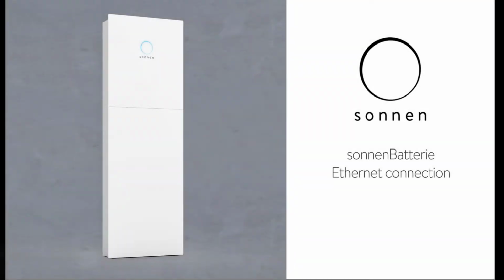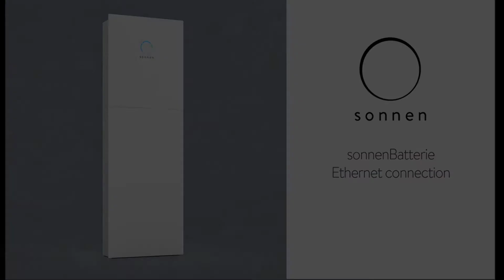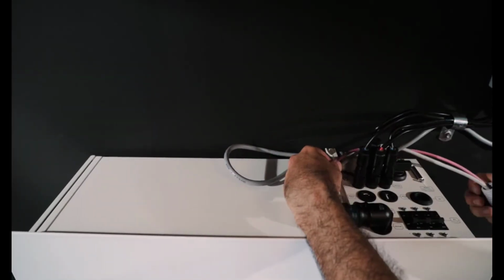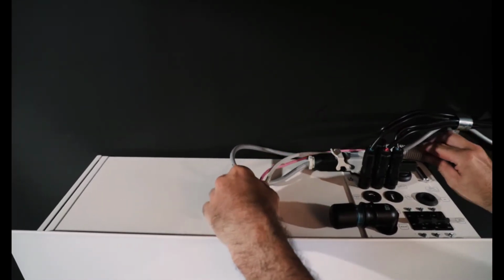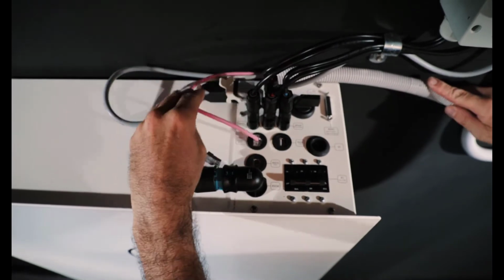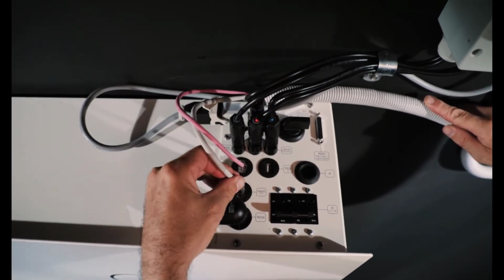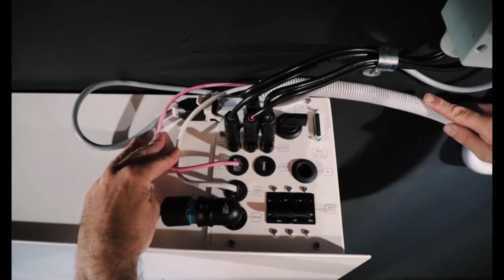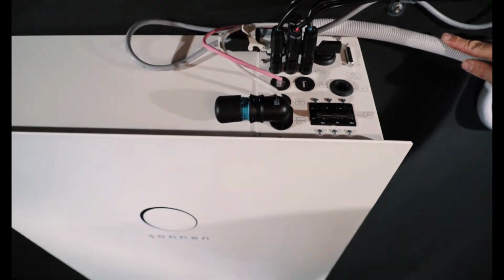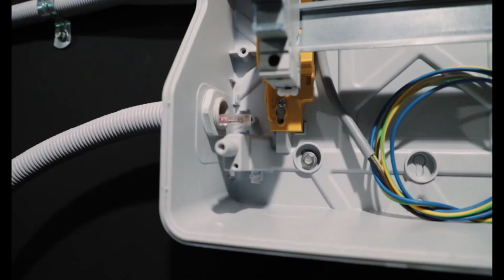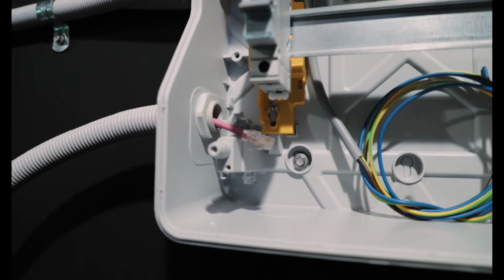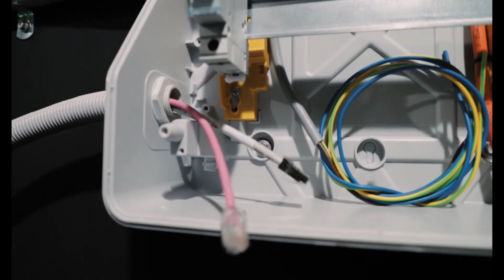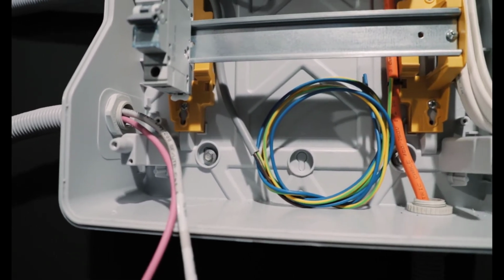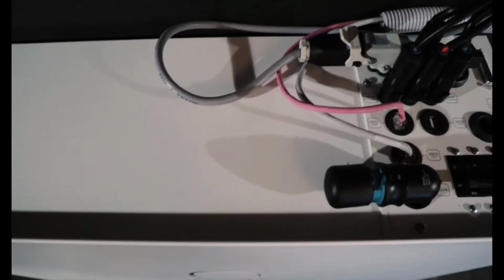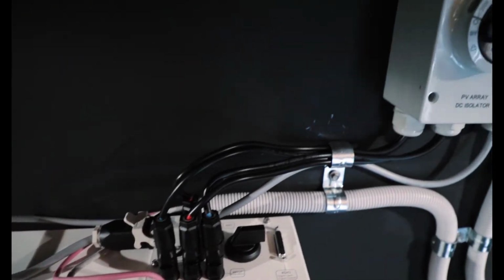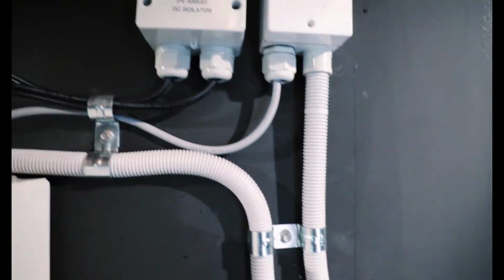So before we go on to any of the metering and CTs, let's have a quick look at the Ethernet connection. What I'm illustrating here is both the Ethernet and the Modbus connections. Ethernet being the grey one, Modbus being the pink, the C-bus cable, because the C-bus cable obviously is terminating within the switchboard. Both need to be rated to the voltage within the switchboard because they're passing through it. The labels at the top of the sonnenBatterie system are very clearly labelled so that you know which is which.